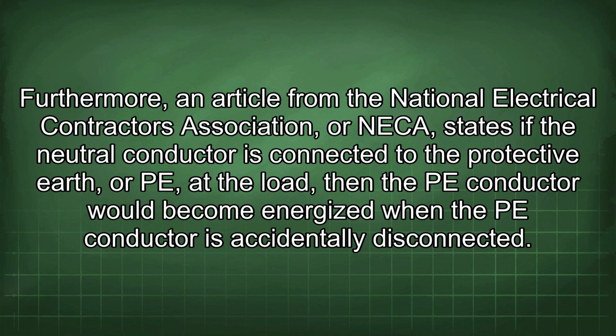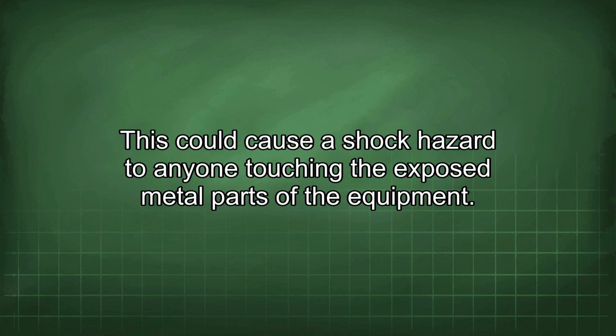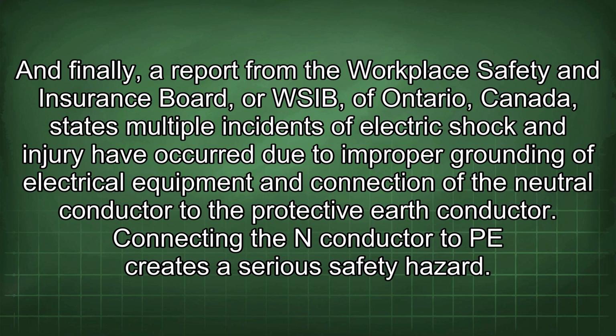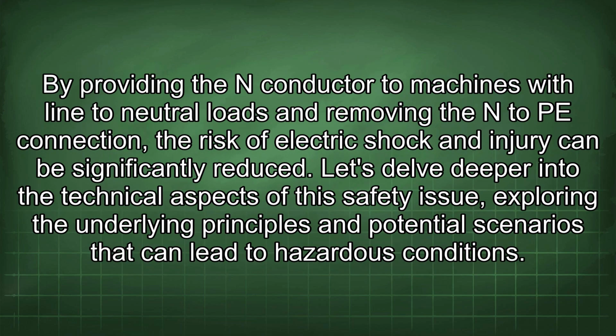Furthermore, an article from the National Electrical Contractors Association, or NECA, states if the neutral conductor is connected to the protective earth, or PE, at the load, then the PE conductor would become energized when the PE conductor is accidentally disconnected. This could cause a shock hazard to anyone touching the exposed metal parts of the equipment. And finally, a report from the Workplace Safety and Insurance Board, or WSIB, of Ontario, Canada, states multiple incidents of electric shock and injury have occurred due to improper grounding of electrical equipment and connection of the neutral conductor to the protective earth conductor. Connecting the N conductor to PE creates a serious safety hazard. By providing the N conductor to machines with line to neutral loads and removing the N to PE connection, the risk of electric shock and injury can be significantly reduced.